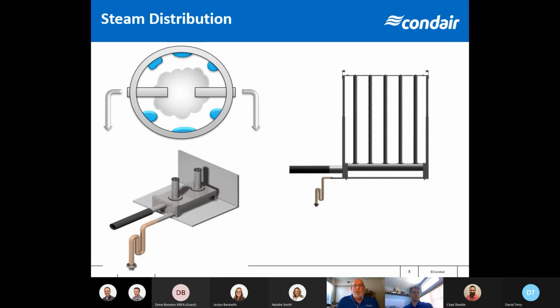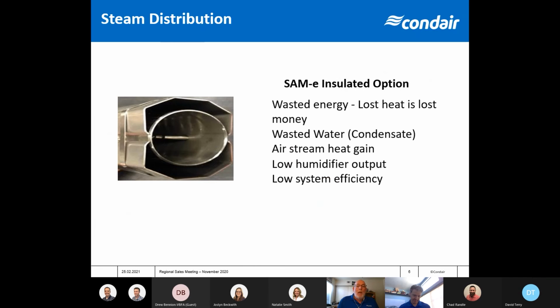It's ejected out of both sides of the tube, spread throughout the whole inside dimension of the duct or the air handling unit. Gives us very, very good absorption. Another thing, we can use these for pressure steam also. When we use them for pressure steam, the header at the bottom of both of these manifolds also acts as a separator, so we don't need a separate separator component when our steam pressure is 15 psi or less.